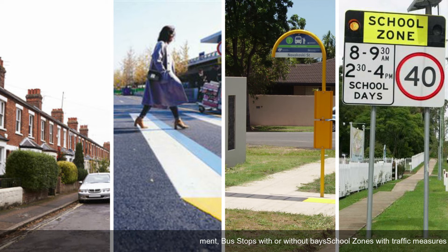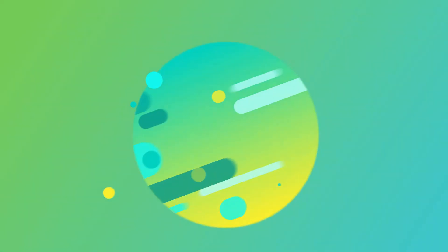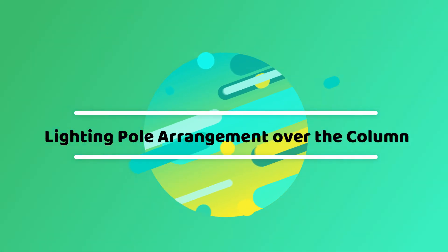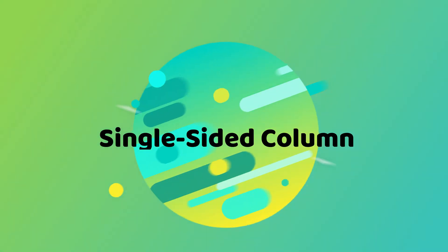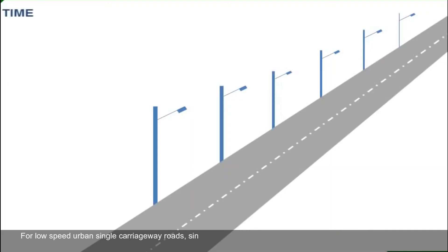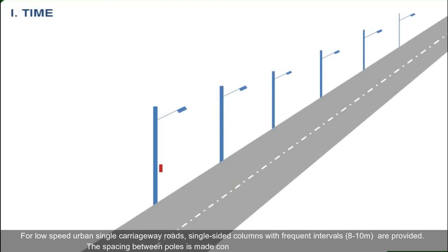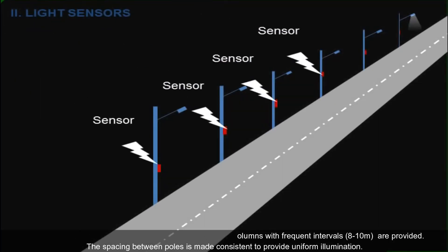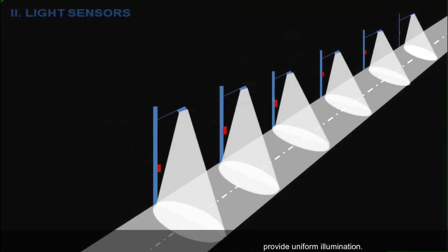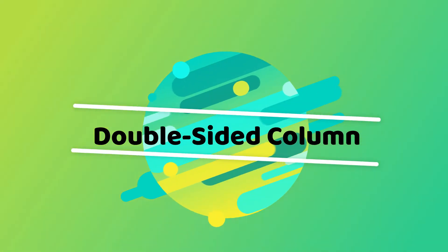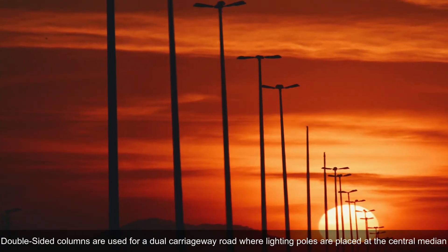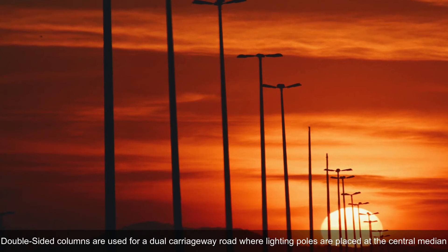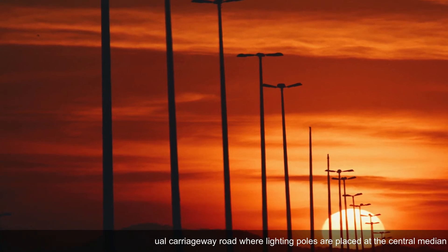Regarding lighting pole arrangement, single-sided columns are used for low-speed urban single-carriageway roads, with frequent intervals of 8 to 10 meters. The spacing between poles is kept consistent to provide uniform illumination. Double-sided columns are used for dual-carriageway roads, where lighting poles are placed at the central median.